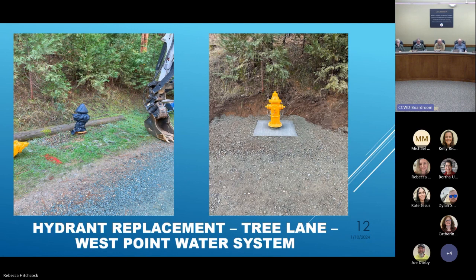You get the flow? So we can, however it's always an interesting consideration when you think about flow testing a fire hydrant, just because of the impact it has on the broader distribution system. We could have a long conversation about flow testing, but yes, we can. Oftentimes we use a pitot gauge, and we can also pull pressure off different hydrants and get an estimation of what the flow would be based on the pressure drop.